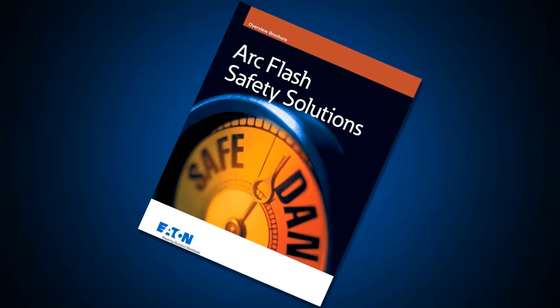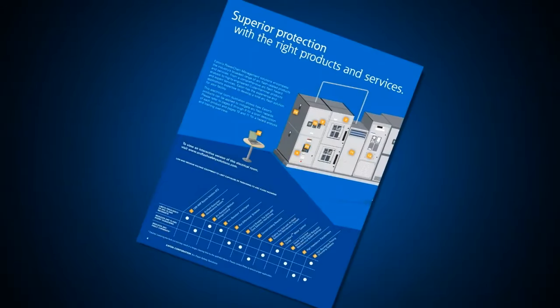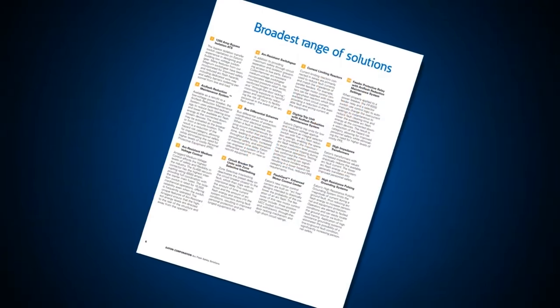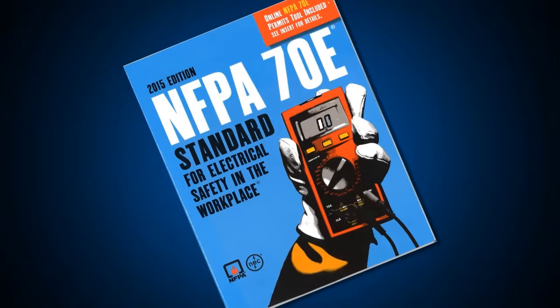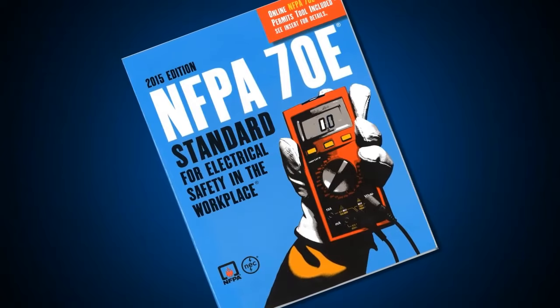These labels are created by our Power Systems Engineering Group, using models of electrical power distribution equipment data from your site with the sizes and settings of your protective equipment taken into account. This ensures that the calculated arc flash levels are accurate for your situation. Our PSC group has done thousands of arc flash studies and applied solutions for our customers' facilities and our own. The NFPA 70E standard serves as a guide defining the method that companies should use to perform arc flash analysis, labeling, and training of personnel.